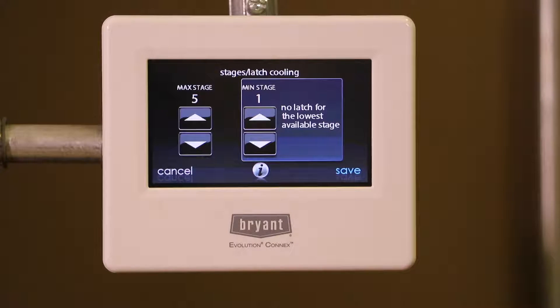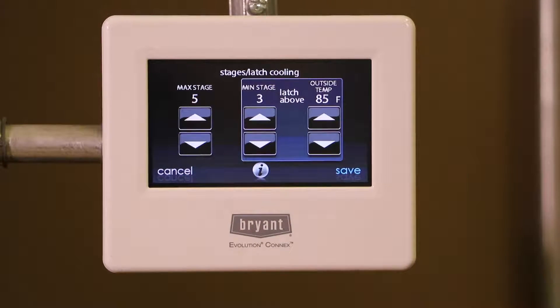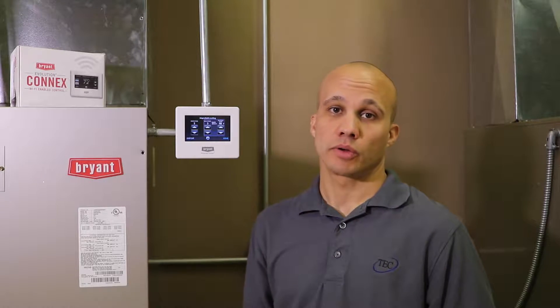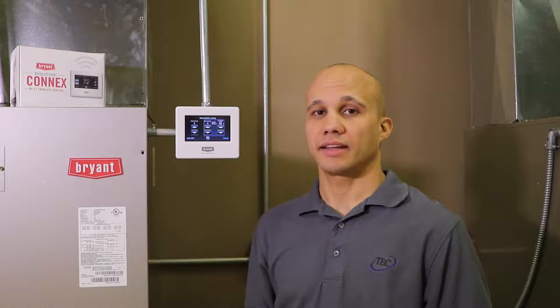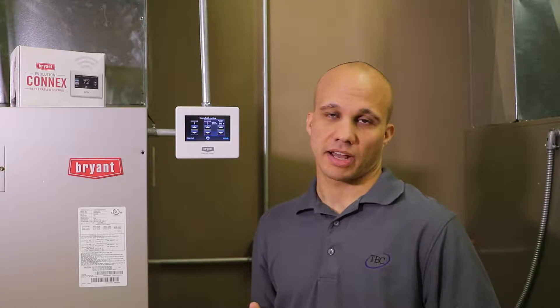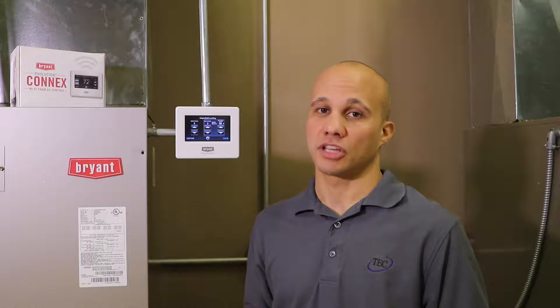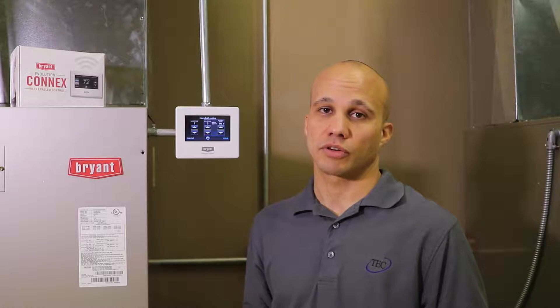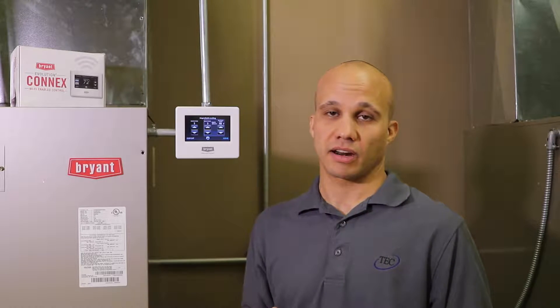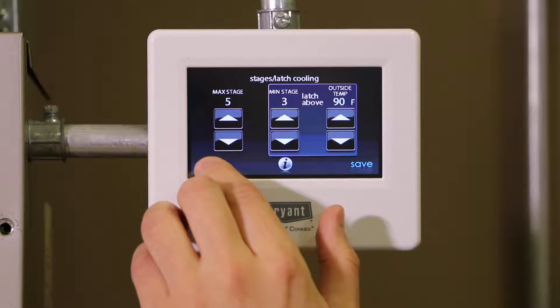The second half of this screen is the minimum staging. This works a little bit differently than max staging. For example, if I pick stage three minimum and I select 90 degrees, what that means is if it's 90 degrees outside we will only run in stages three, four, or five — we will skip stage one and two. The whole idea with that is there might be times when it's really hot outside, above 90 degrees for example, when the thermostat is satisfied on stage one or two because it's downstairs, but maybe I'm not getting enough air to the upstairs. By forcing it to run stage three, four, or five only, that forces more CFM out of the air handler which forces more air to the upstairs zone. I don't want to make any changes here so I'm just going to hit cancel and go back.